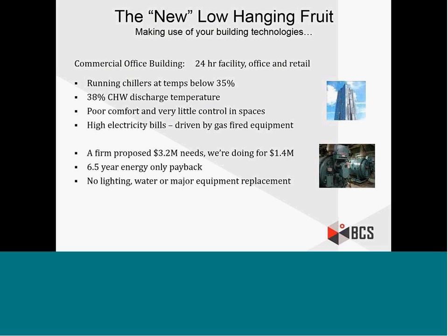They had a lot of constant volume boxes out in the space, so we converted the constant volume boxes to VAV with a controls upgrade to give them a lot more control. We didn't do any major new equipment — no new chillers, boilers, or anything — and no lighting work. It was mainly controls retrofit in the boxes, and then we put in a plate and frame heat exchanger.